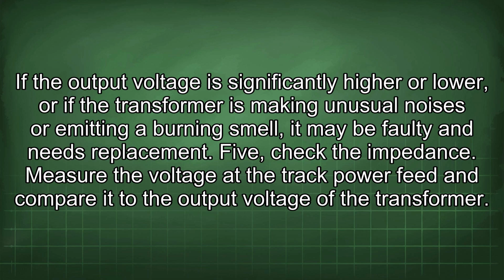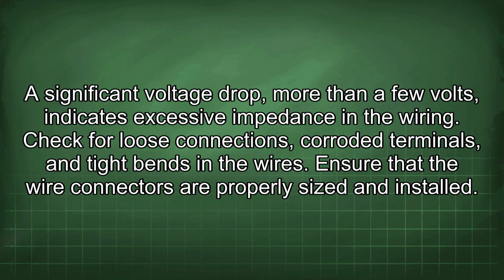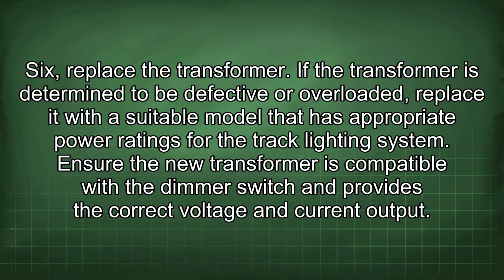5. Check the impedance. Measure the voltage at the track power feed and compare it to the output voltage of the transformer. A significant voltage drop, more than a few volts, indicates excessive impedance in the wiring. Check for loose connections, corroded terminals, and tight bends in the wires. Ensure that the wire connectors are properly sized and installed. 6. Replace the transformer. If the transformer is determined to be defective or overloaded, replace it with a suitable model that has appropriate power ratings for the track lighting system. Ensure the new transformer is compatible with the dimmer switch and provides the correct voltage and current output.